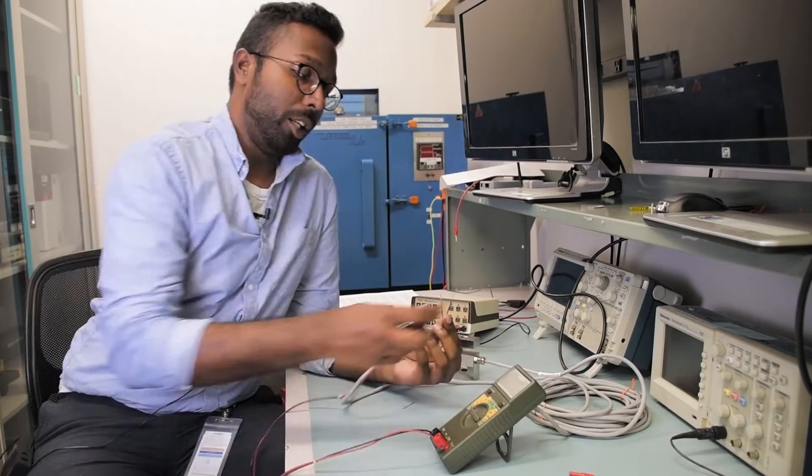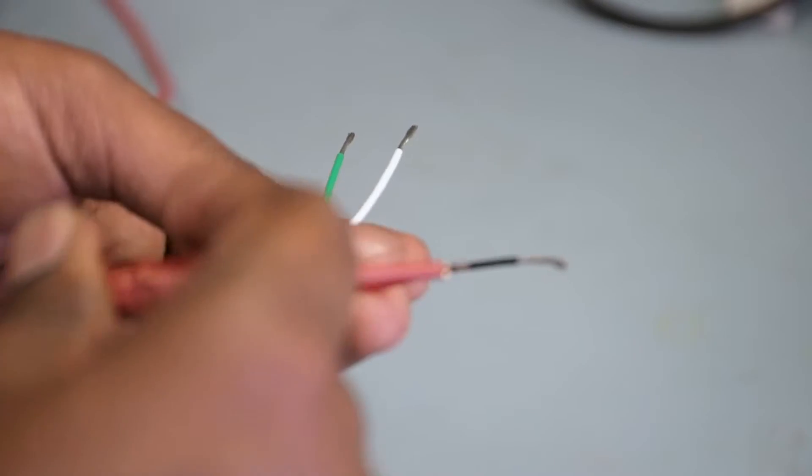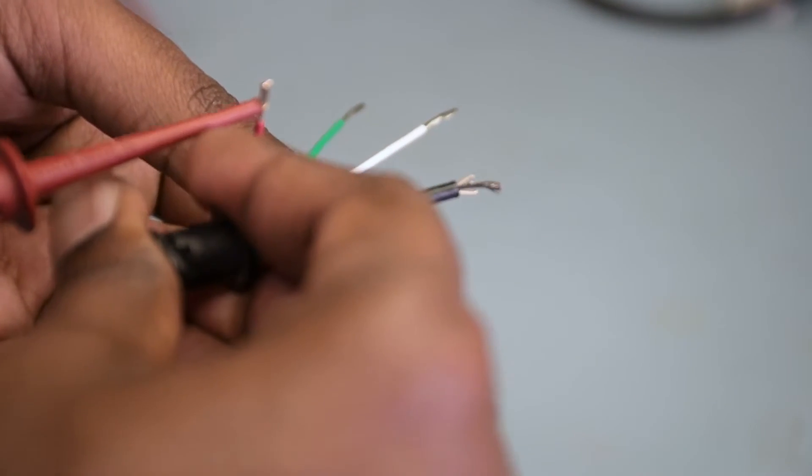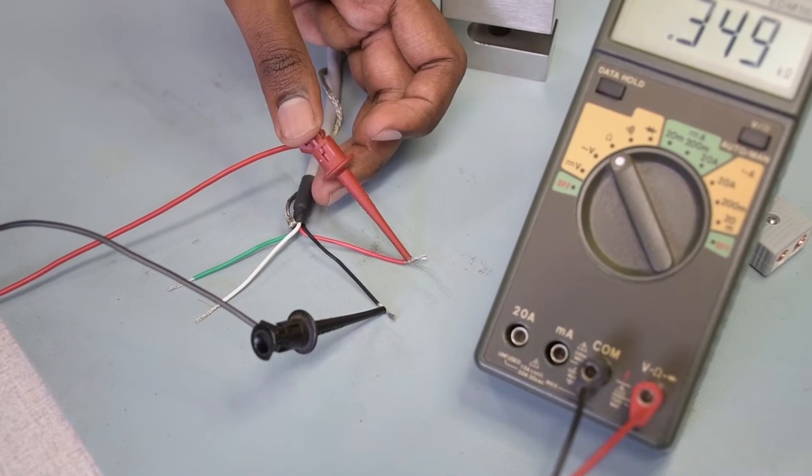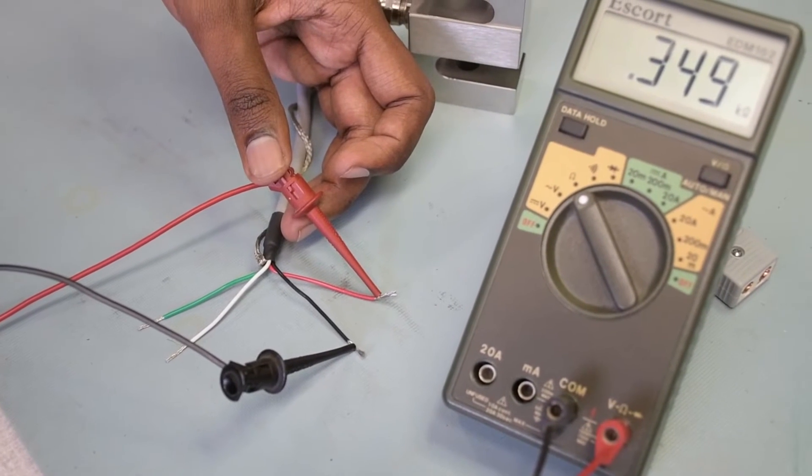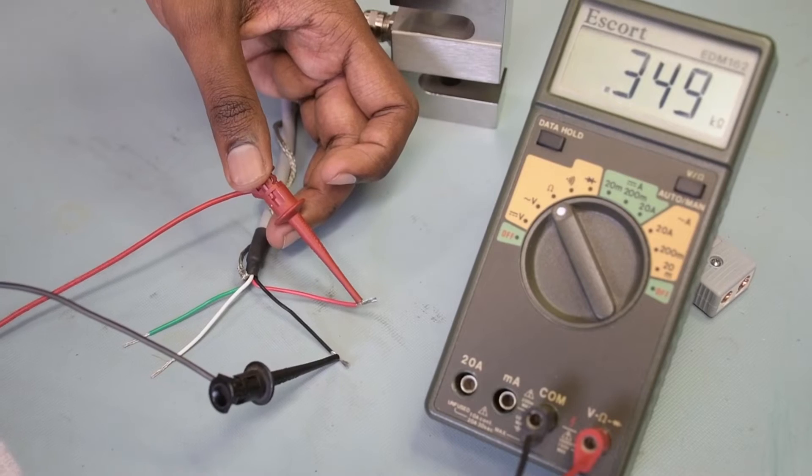So take your multimeter and measure the resistance across the two input leads. In this case, my input leads are red and black, and set your multimeter to read in ohms. My input resistance should be close to 350.10 ohms, and I'm reading 349 ohms, which is fairly close enough.